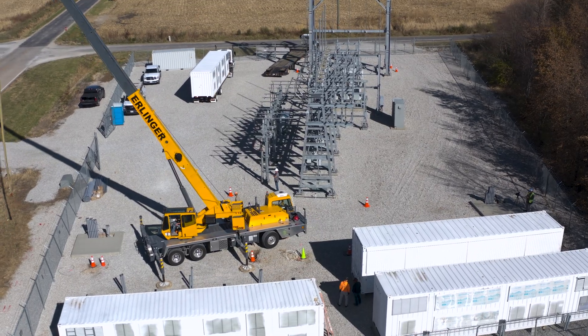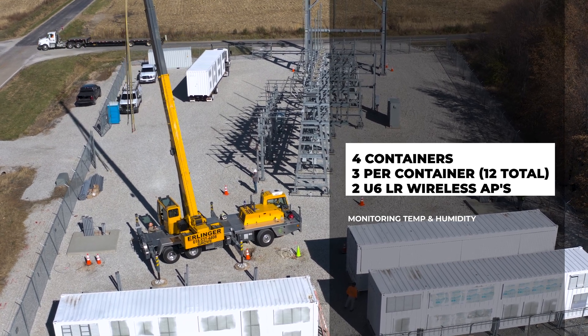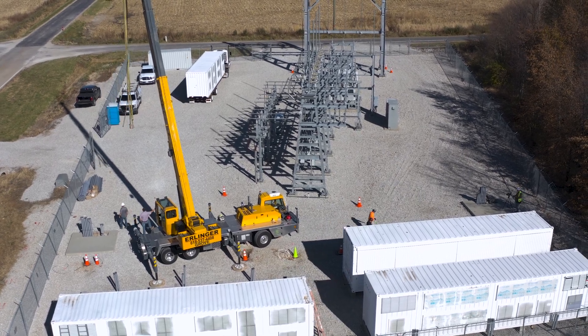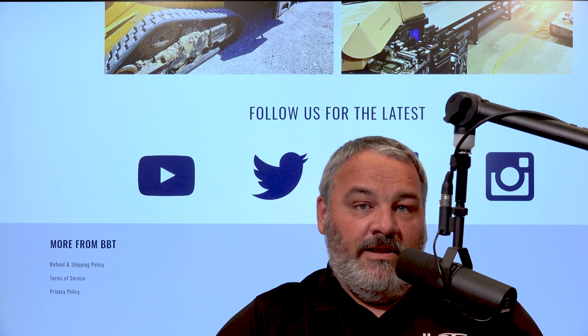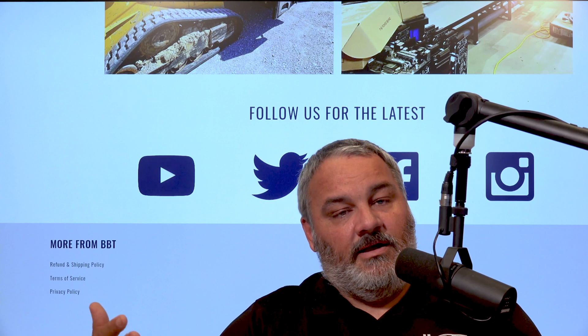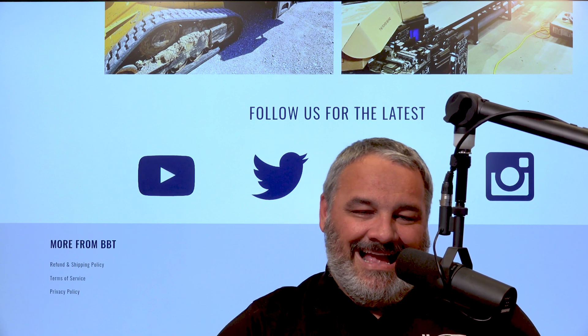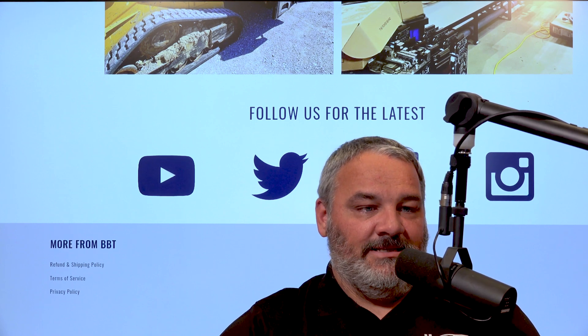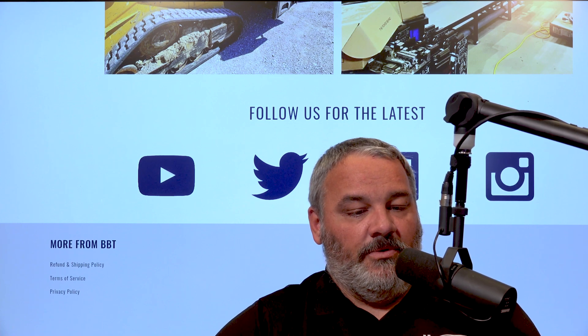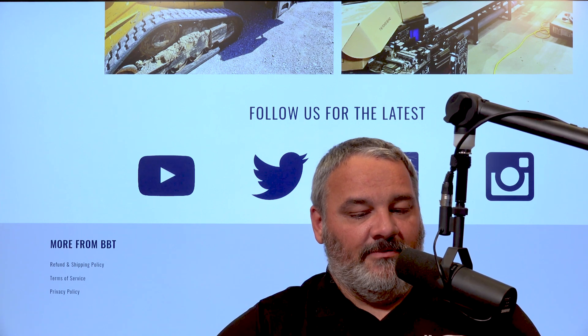We got 12 of these and we're going to have two U6 Long Range units deployed into the two containers. These are 40-foot containers and they're about 12 feet apart from each other, so you're talking 52 feet from the farthest potential sensor to the next set of sensors in the farthest container. Bluetooth isn't really that good past around 60 feet, and that's in a clearing, so you really need coverage with a couple of units if you're spreading out that far. I'd always say start with one unit and see if it makes it.